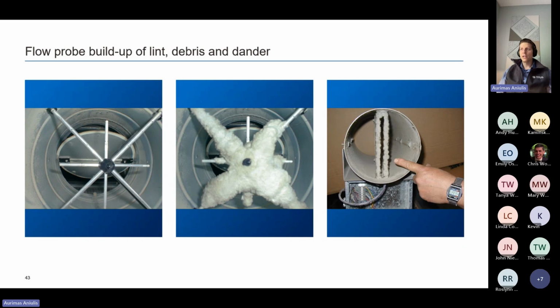Well, that's when you climb up the ladder, cut the ductwork open, clean out the sensor. And if you're smart, you're going to put a permanent clean out door unless you're going to change the airflow control device, right? Same with these two pitot tubes in here, right? This is just regular dust and debris that you find in general exhaust, and it's going to foul up your sensors in the airstream. I had a project in Latin America where we had this very same conversation. I showed them these very same pictures, and they went for the lower upfront cost of VAV boxes.